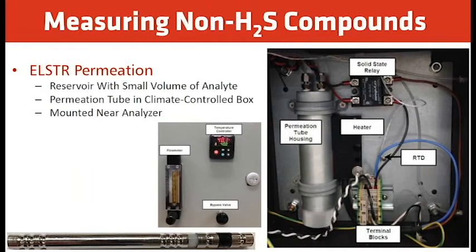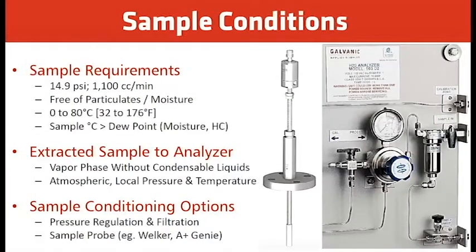The ELSTR permeation device is a reservoir with a small volume of analyte, mounted in a climate-controlled box near the analyzer. By maintaining a constant temperature, the permeation rate stays consistent regardless of ambient temperature fluctuations. If you know the temperature and flow rate, the concentration will stay the same without any variation.